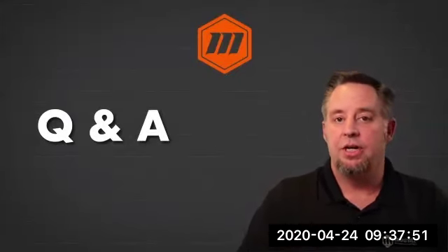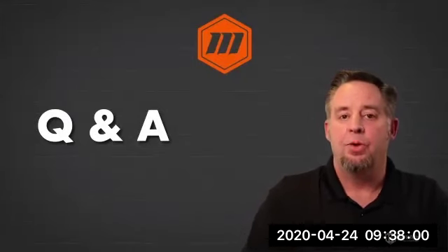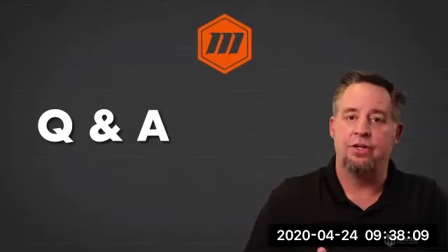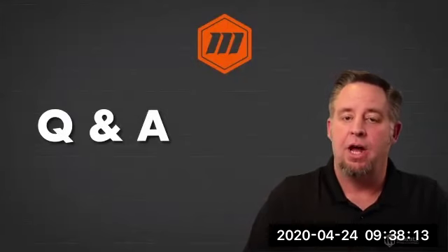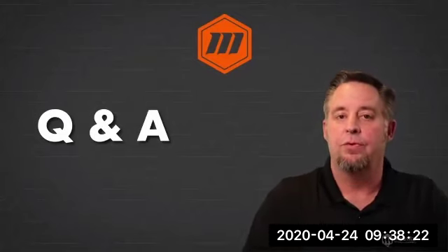Okay. Next question was, what is a good threshold percentage to identify a tool drifting out of tolerance and trigger it to be recalibrated? That would be determined by the requirements for your specific application. If plus or minus 10% of the torque value is what you want to go with, then you could set your tool up to make sure that it stays within that tolerance. That could fluctuate anywhere from 5% to 6, 10, 15. It just depends on the application and how critical the torque is for that specific joint. So it would be determined by your specification for your specific part.